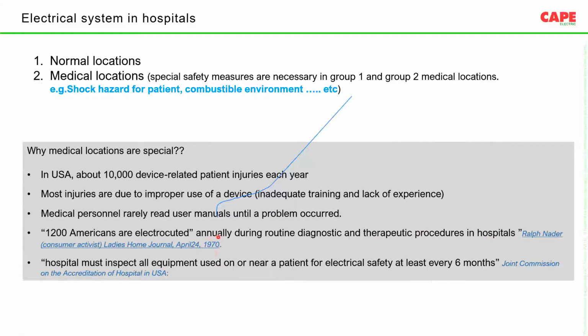This is very old data, 1970 data. So they had problems, and even at that time they realized the problem. As a result, they started developing standards exclusively for the medical location, because a medical location, especially a patient area, an operation theater, or a place with ICU and a lot of electromedical equipment, needs a very special classification. You can see here, medical personnel rarely read the user manual until a problem occurs, because the hospital orders an equipment, the supplier will come and install the equipment, and mostly the safety part is neglected.